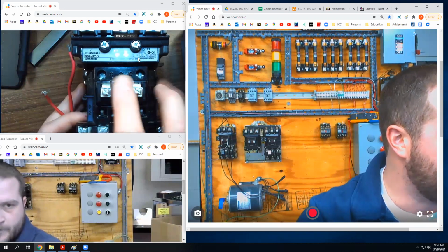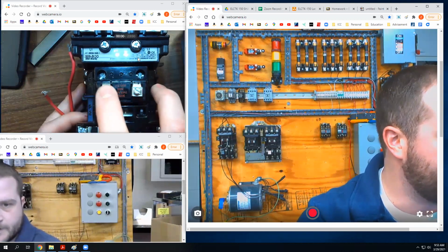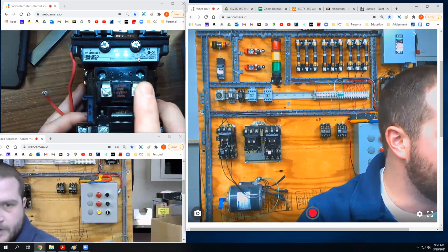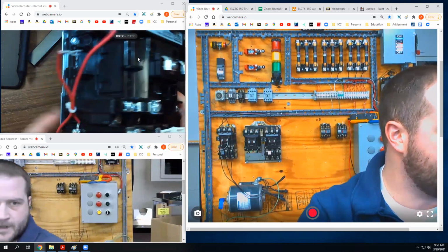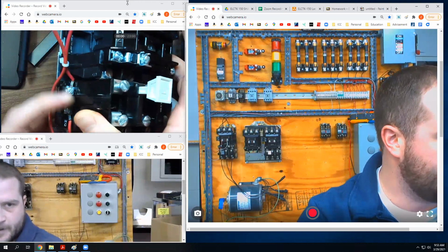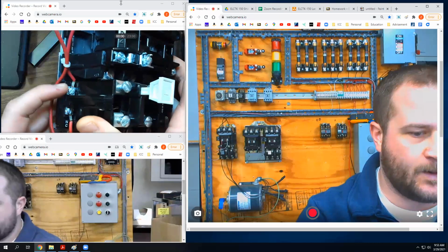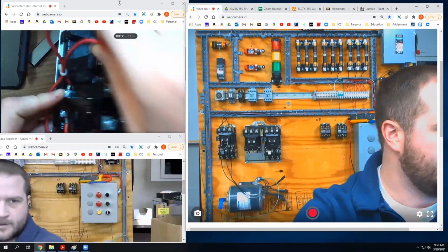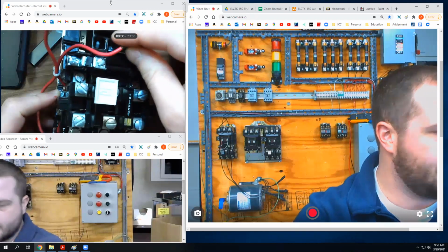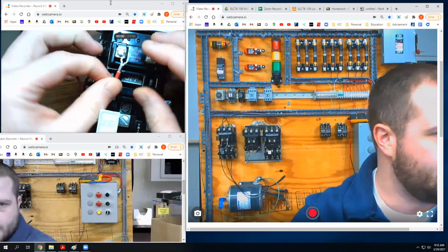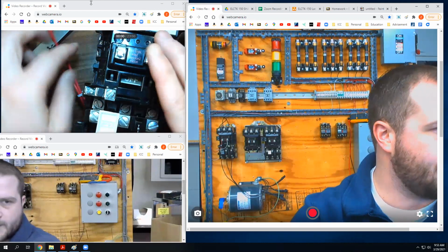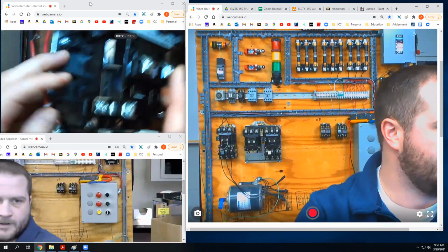So I've got a wire number 4 going to this place, and I need a 2 coming from here and going over to the side to this normally closed contact right here. That's actually what this little jumper, put on there by the factory, is there to do. But I'm going to take a white wire and go from here to here, and actually that's already done on my trainer.